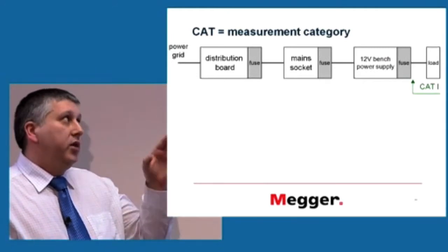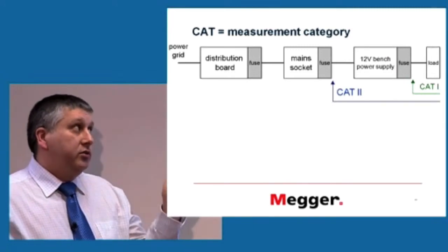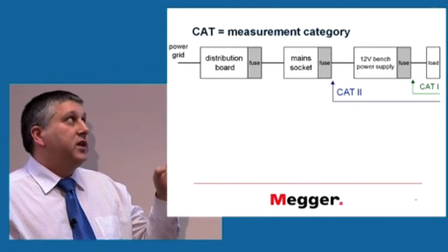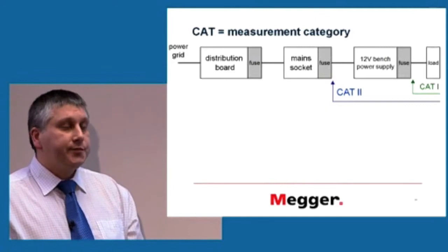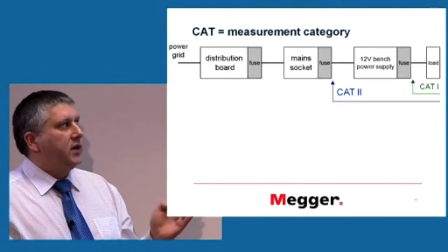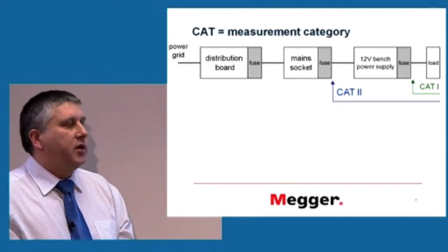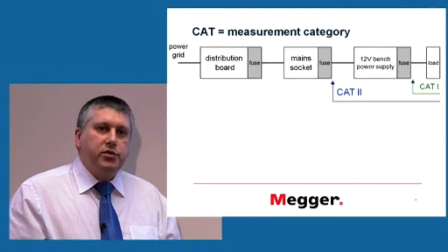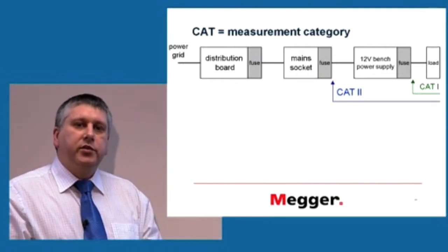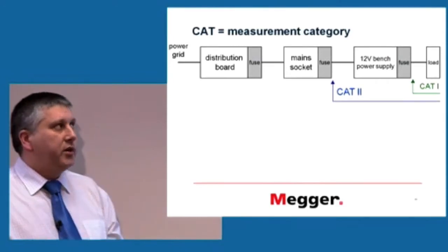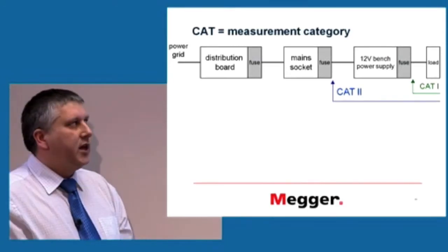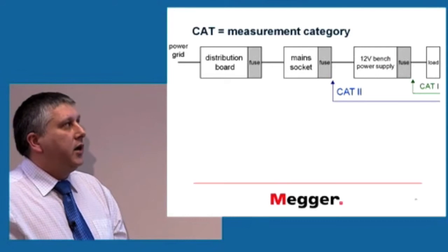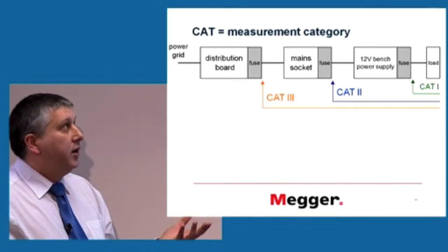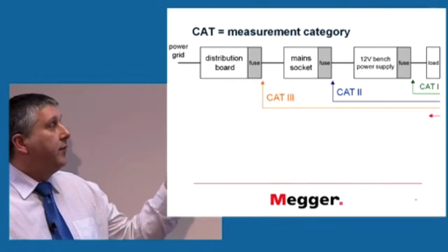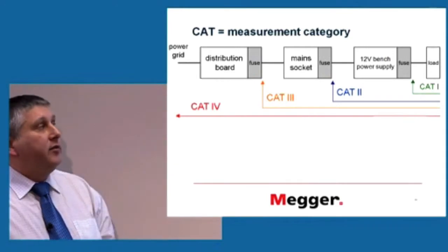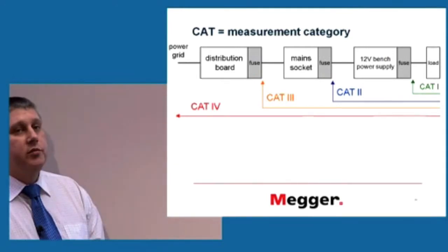CAT2, let's say measurement category 2, is stated for something which can be used at mains voltage. And obviously, there has to be a voltage stated at which voltage we are talking about, because, for example, in the States they use lower voltages, 110 volts, as opposed to Europe, which is 240 volts. So also that has to be stated. And then if we go higher, there will be measurement category 3. And measurement category 4 is something which is measured above or beyond the distribution board and the circuit breaker.